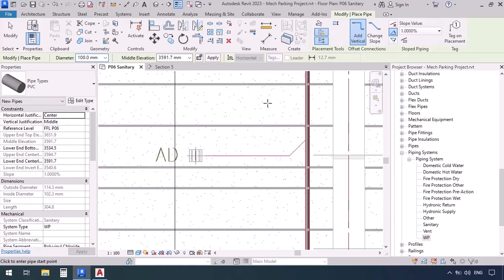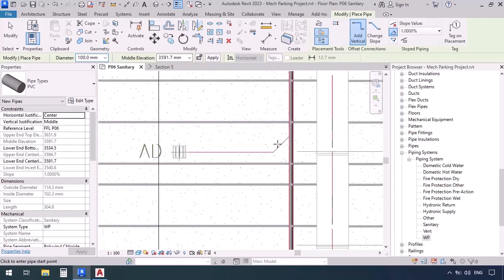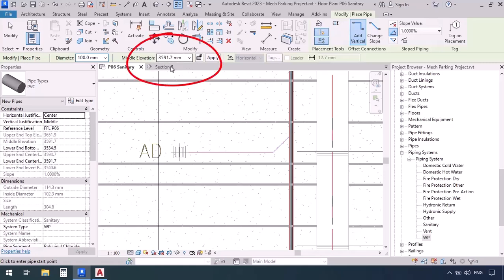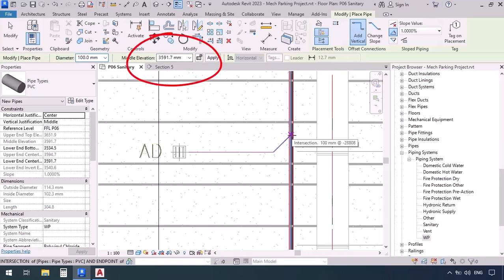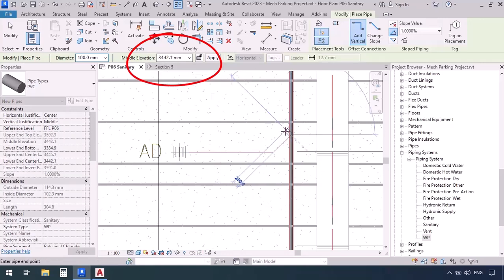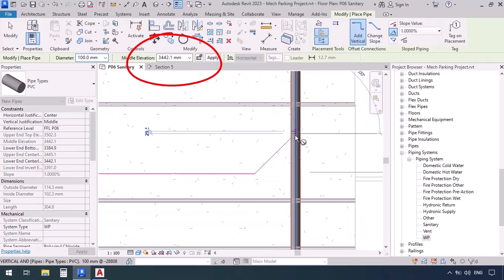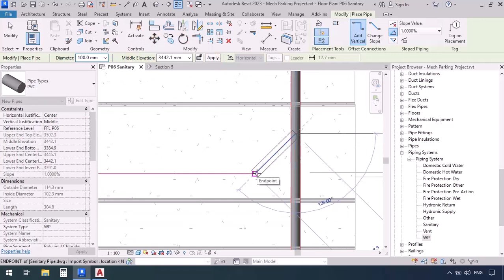Always remember: when you're getting close to the drain, you use slope up; when you're going farther, it's slope down. Keep this in mind as a rule so you don't make any mistakes. Now the slope is going up. I'm going to click on the pipe. Check out the elevation — it's 3591. Once we click, it changes to 3442, so it just inherited the elevation from exactly the point we clicked on.